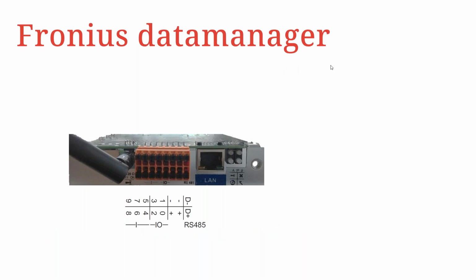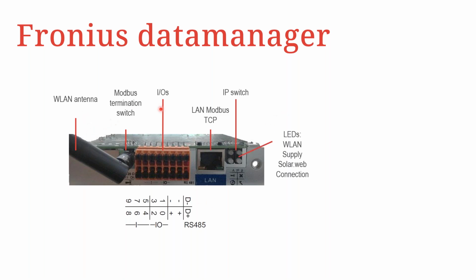In terms of the data communication, if you're using the data manager, this would allow you to communicate with the Fronius, the Victron Color Control GX. And in addition to that, it would allow you to connect internet to the Fronius inverter for you to be able to send the required data to Fronius SolarWeb for monitoring. So this is an illustration of a Fronius data manager card. These are the various communication ports that are available. We have here the Modbus TCP or LAN Ethernet, and this is the connection that would allow you to connect to the Color Control GX, for example, through a router.